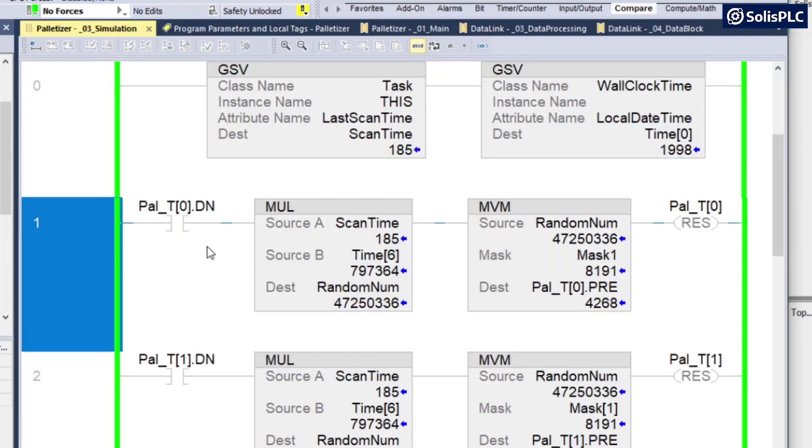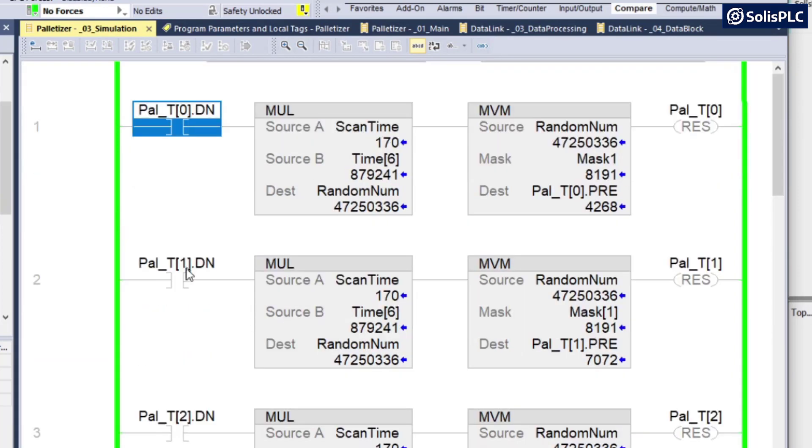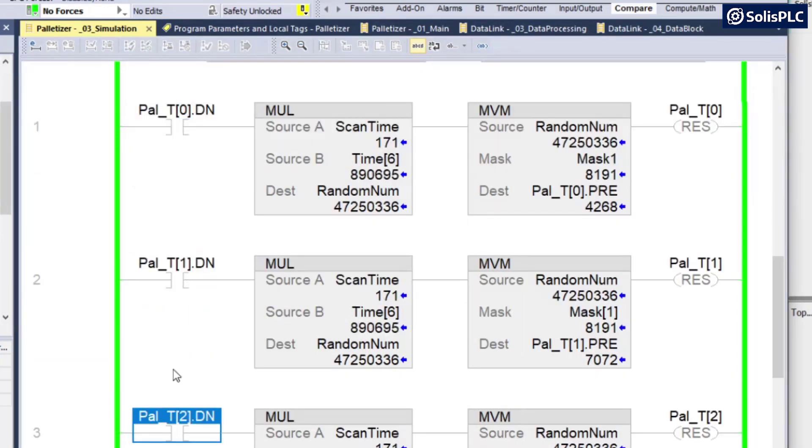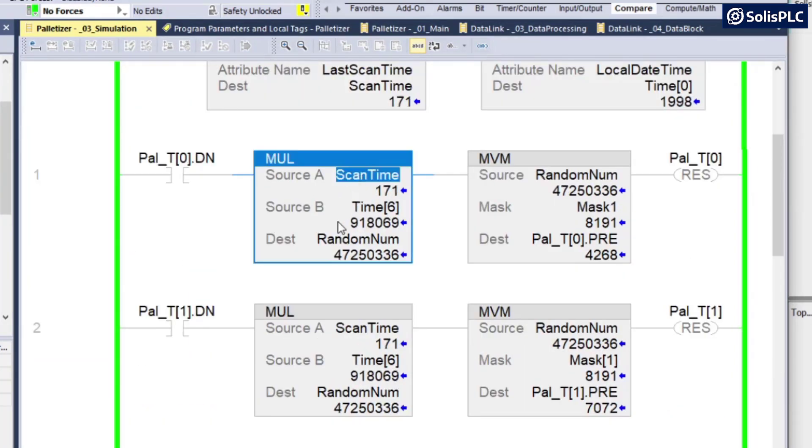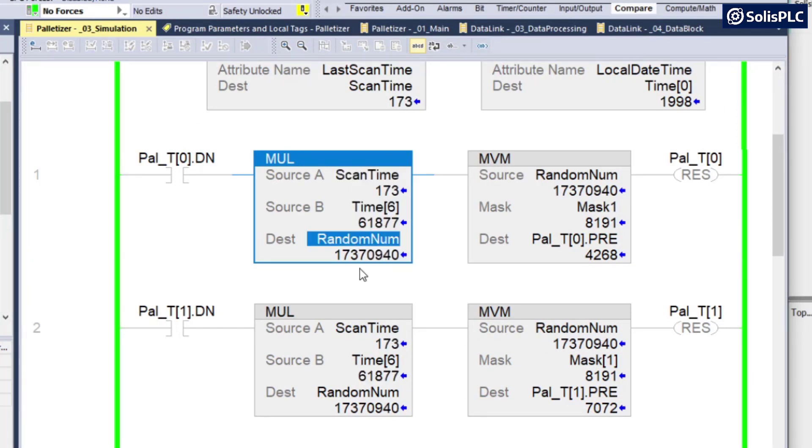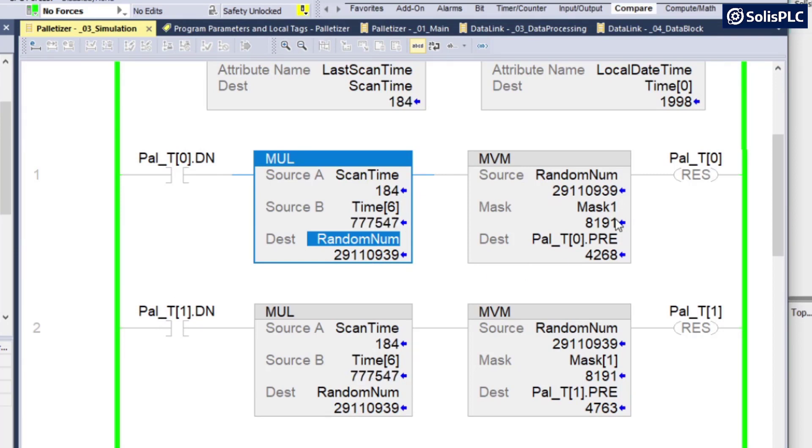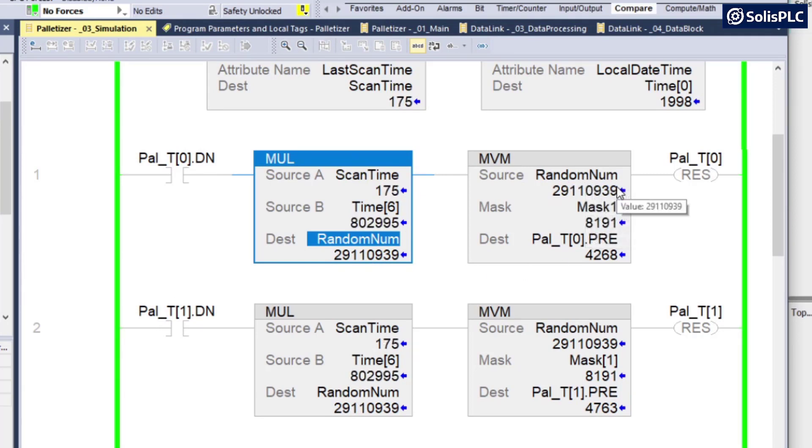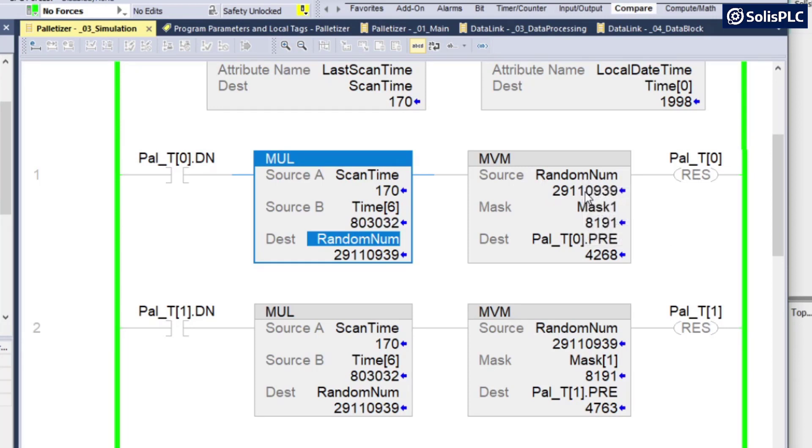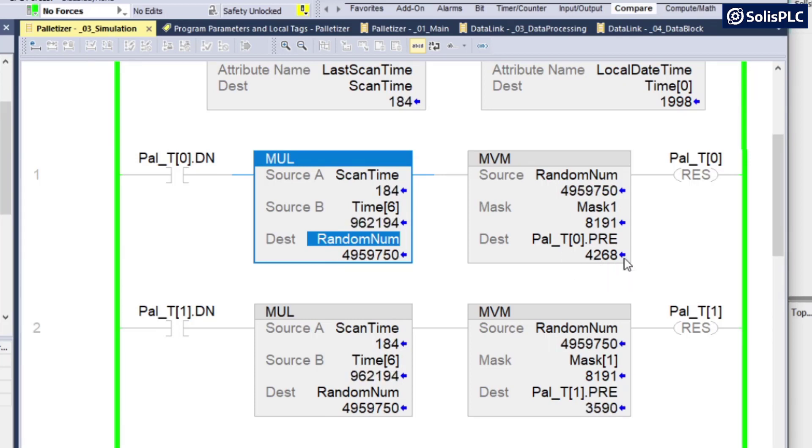Going back to the logic, what I'm doing here is once any of the timers is done, so timer zero, timer one, timer two, it's going to multiply the scan time by the number of microseconds, thus resulting in a very large random number that's always going to be different. As you can see, it changes once one of these is being triggered. And what I'm doing is that I'm moving the number, this random generated number through a mask to give me a time value from zero to a certain number that's going to be dictated by my mask.